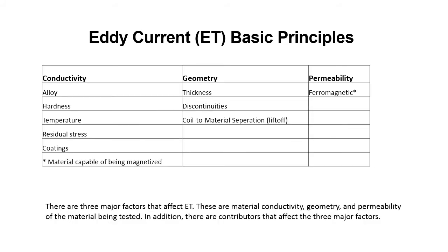There are three major factors that affect Eddy Current Testing. These are material conductivity, geometry, and permeability of the material being tested. In addition, there are contributors that affect the three major factors. Conductivity can be affected by alloy, hardness, temperature, residual stress, and coatings. Geometry: thickness, discontinuities, coil-to-material separation. And then permeability — is it ferromagnetic? These are things that need to be taken into consideration by the Eddy Current Testing Technician.